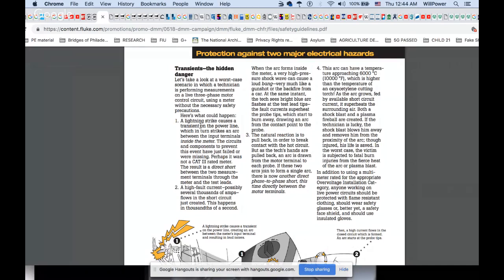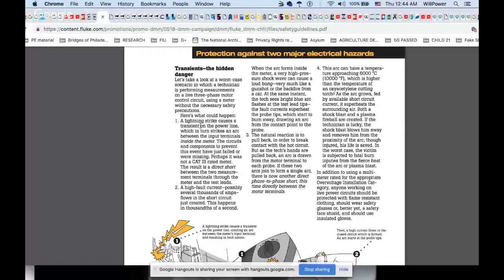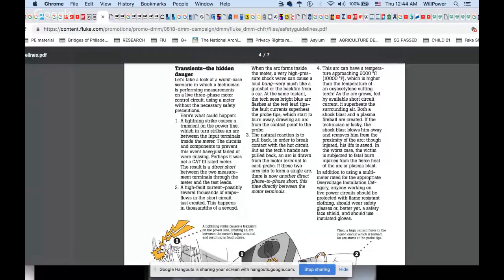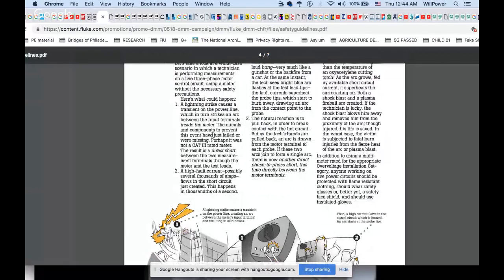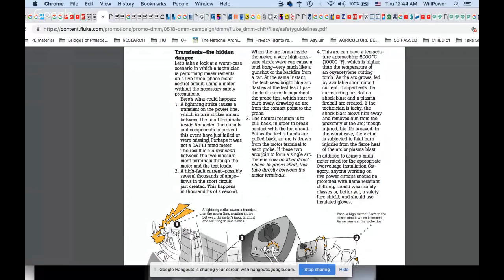Here's what would happen: a lightning strike causes a transient on the power line, which in turn strikes an arc between the input terminals inside of the meter. So inside the meter, the circuits and components to prevent this event have failed or were missing. Inside your cheap meters, Harbor Freight meters, they're not there.